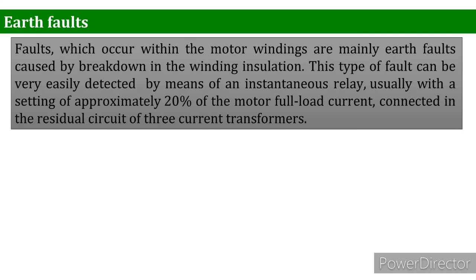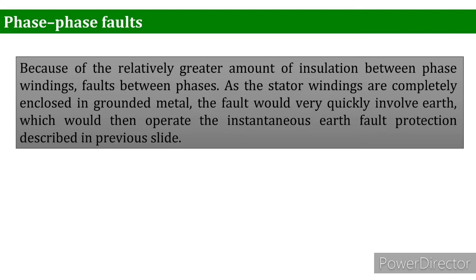So an earth fault can happen on the motor, but it is not very difficult to eliminate. The other one is phase to phase fault. As we all know, there is a greater amount of insulation between phase windings, so phase to phase faults are less common in the three-phase system. As the stator windings are completely enclosed in grounded metal, the fault would very quickly involve earth, which would then operate the instantaneous earth fault protection. We can also have differential protection.